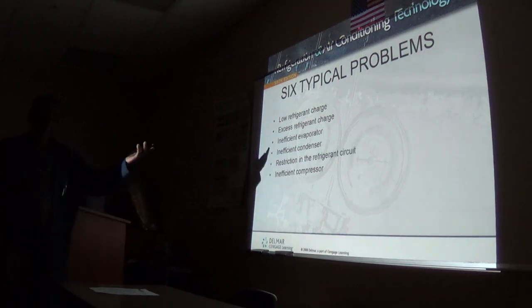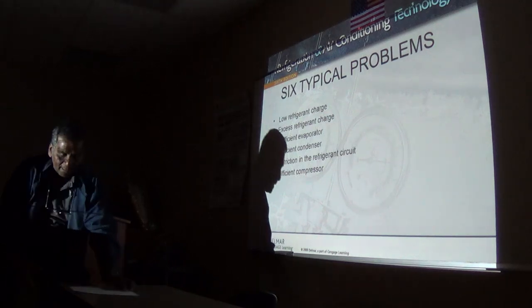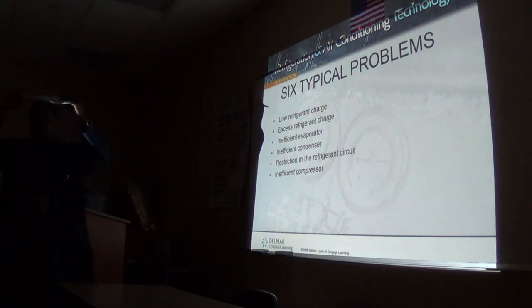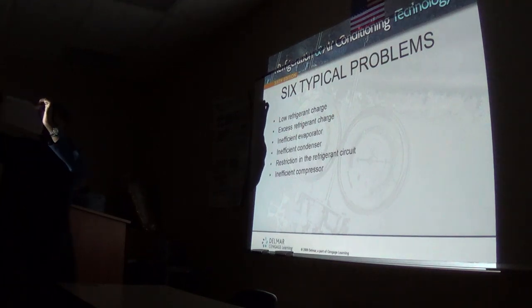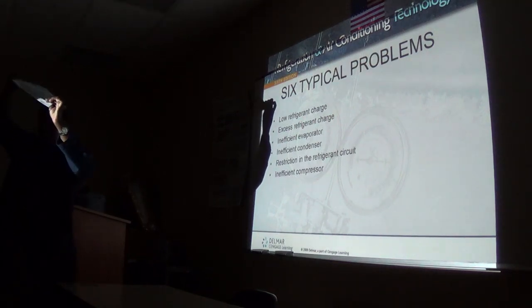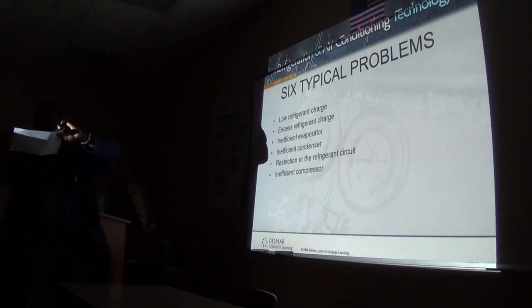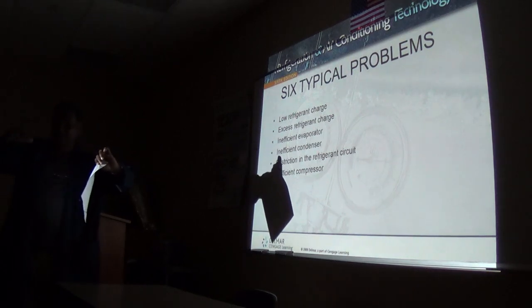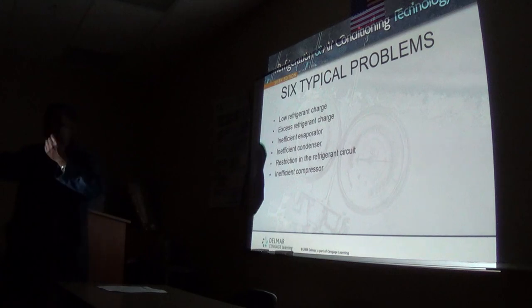Yes, it's just normal wear and tear, and most of the time it's the valves. These are reed valves in those compressors, thin like this sheet of paper. One side is bolted down, and the other side moves up and down as the piston moves up and down. Over a period of time, it loses that spring action and gets worn out because it's slamming onto the seat. So there will be refrigerant leaking back.